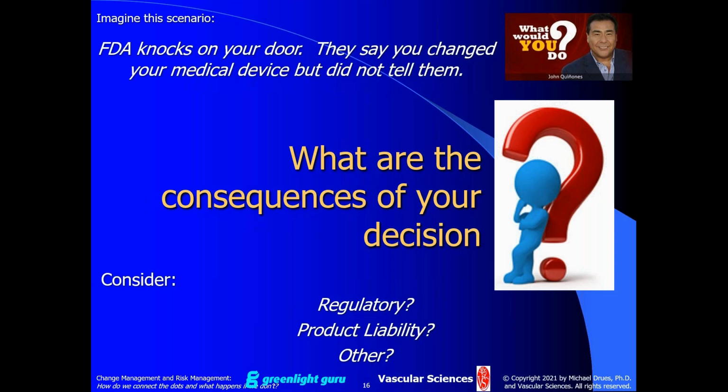You probably have handled that via what we call a letter to file, right? So is the justification that you put in your letter to file sufficient? Is it strong enough to defend your position of doing this as a letter to file, or should you have notified the FDA in terms of either a special 510K or a PMA supplement, depending on how your device is on the market?